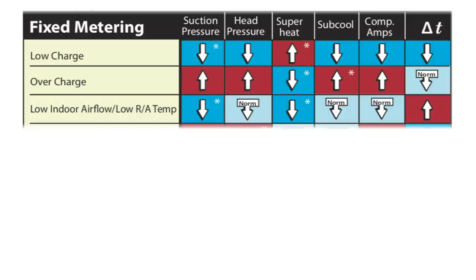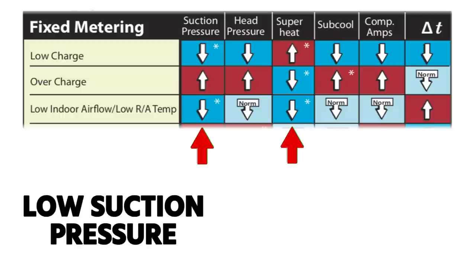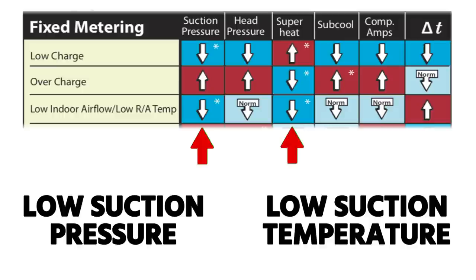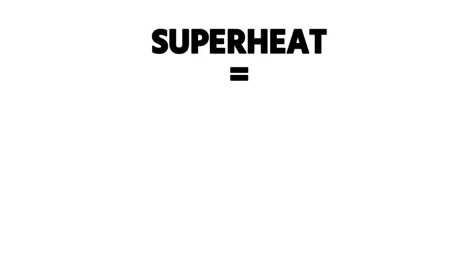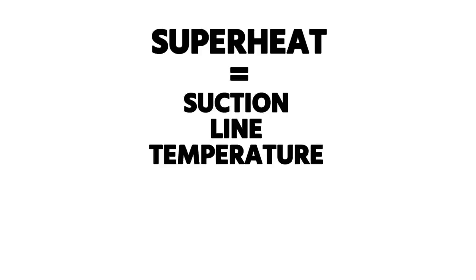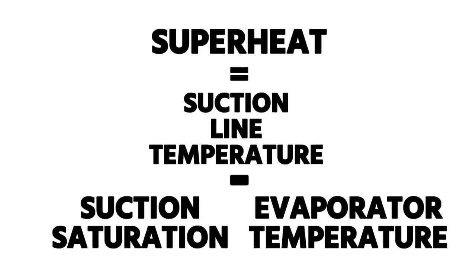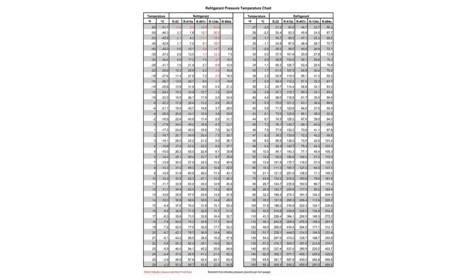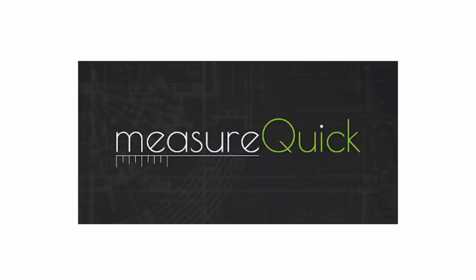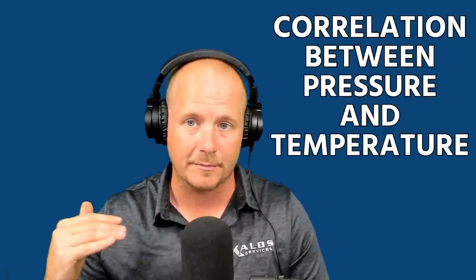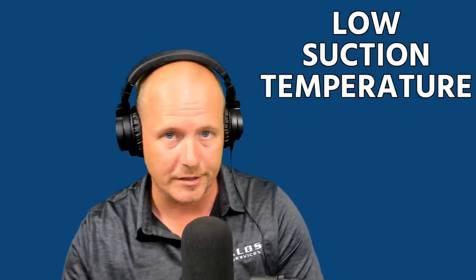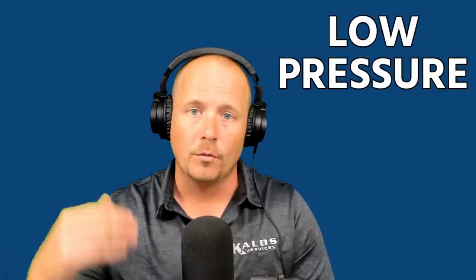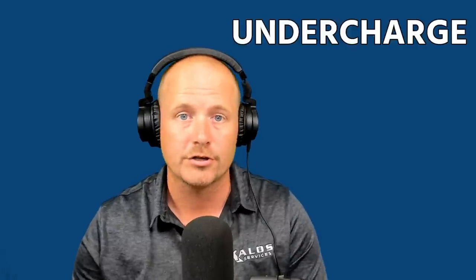When you actually connect to the system, what the chart shows is you're going to see low suction pressure and low superheat — meaning low suction pressure and low suction temperature. Superheat is your actual suction line temperature minus your suction saturation temperature, which you get from a PT chart, an app, or MeasureQuick. That differential — low suction temperature and low pressure together — differentiates low airflow from other causes of low suction pressure like undercharge or a restriction.